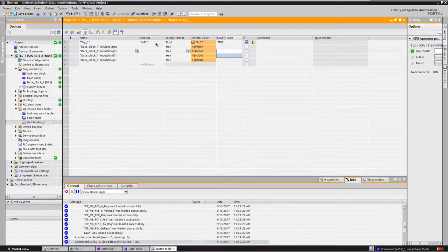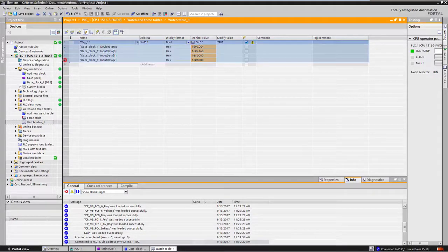The first 2 registers of the input data correspond to the value. The high byte of the last register contains the status. Hex 80 means good. If you click several times on Modify Now, you can see how the data changes. Delete all entries.